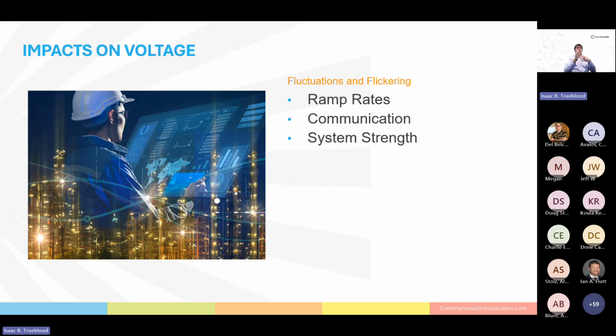A battery added to these systems can solve this problem. However, even a 5-minute battery, that is a battery that can produce 5 minutes of the total site's power, can make distributed energy resources non-financially viable. However, if you control the rate at which it increases its generation, it will greatly reduce the impact. This helps as customers will only experience a brief voltage decrease with the slow return to normal voltage rather than a sudden drop and rise. Additionally, it allows for voltage regulators to experience less wear from chasing sudden voltage increases and decreases.